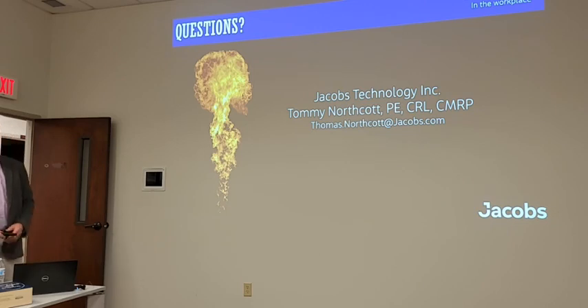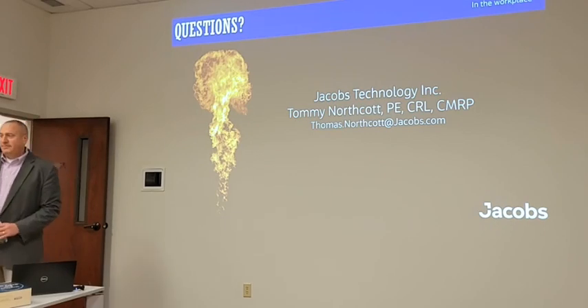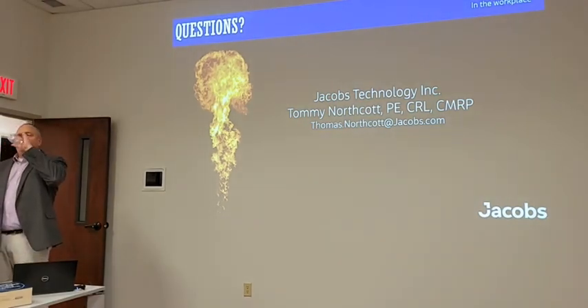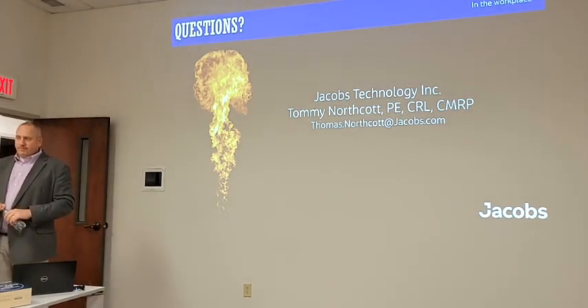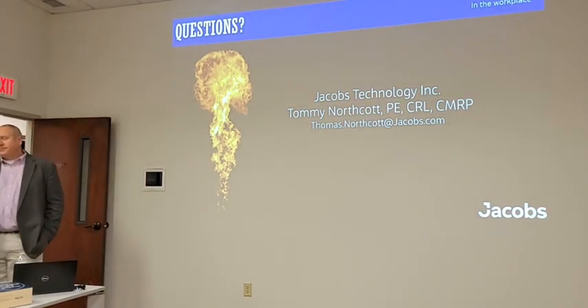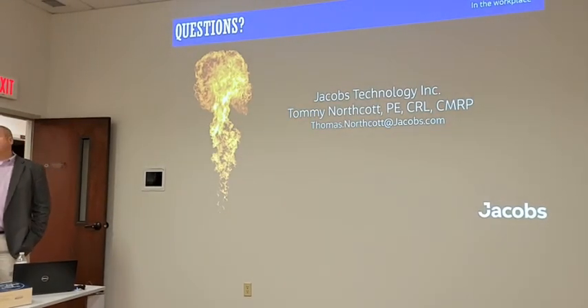Question. Let's say you walk up to an operator control panel, and it's like what we described. It's got drives, a PLC, a flat panel touchscreen, and some push buttons. And it's a large Hoffman enclosure, and it's closed up. And it's got an arc flash hazard level 2. So, is it safe to walk up and push that start button to close the contactor to run the motor? Where's the contactor that's closing? It's inside the enclosure. Then the answer would be no. No. You need the level 2 PPE on.